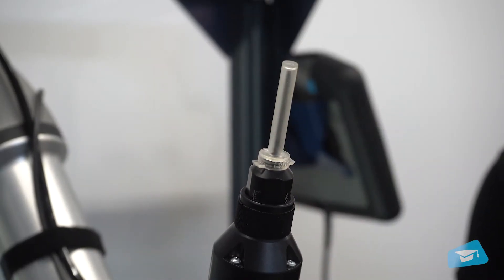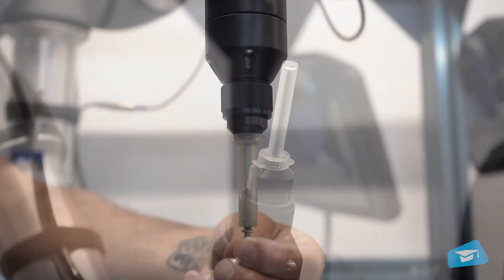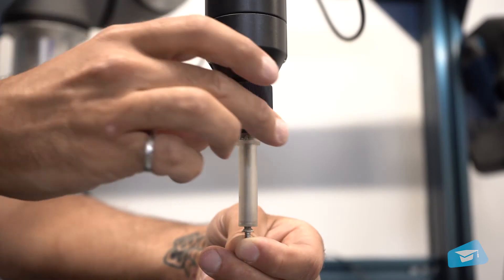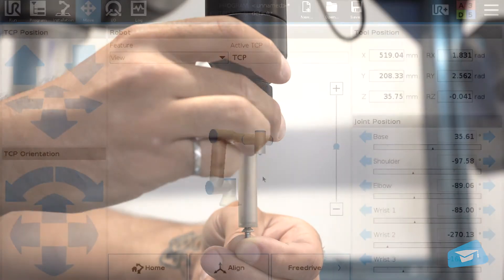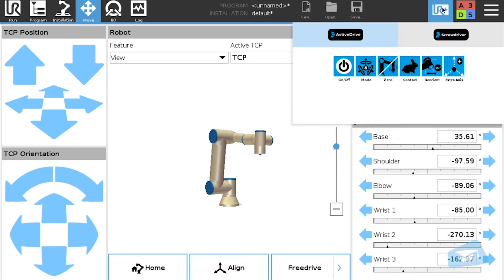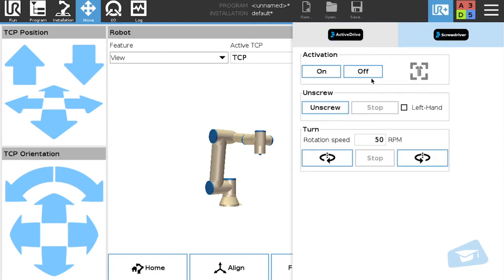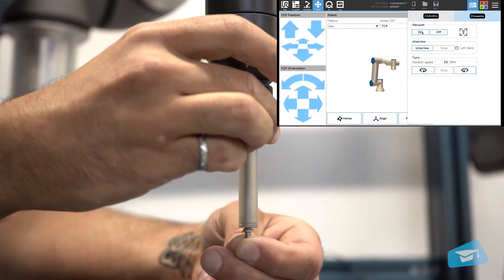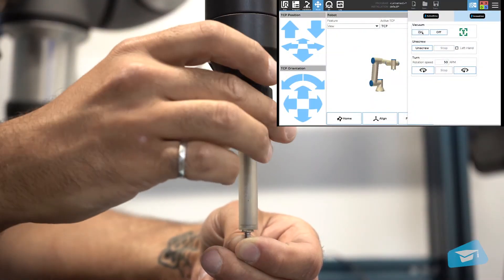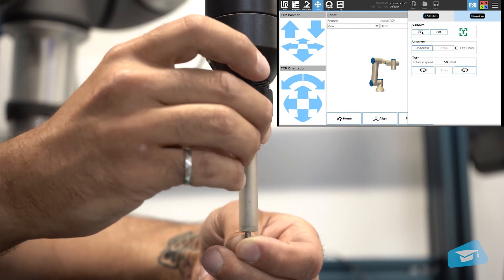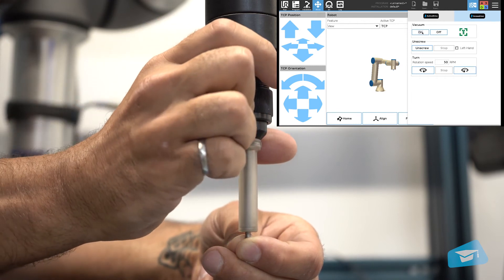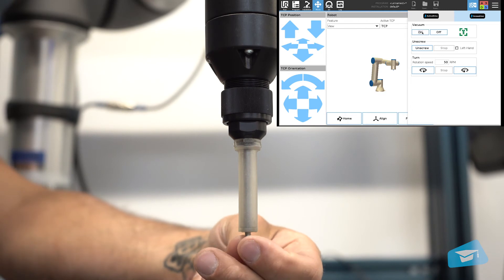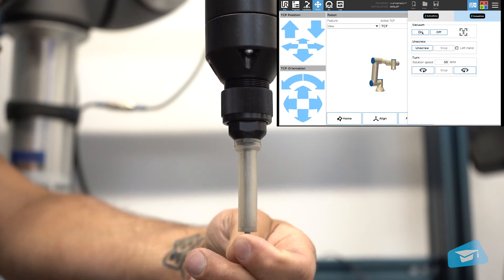The position of the vacuum sleeve in relation to the bit should be adjusted. To ensure a successful screw pickup using vacuum action, start the vacuum action using the screwdriver toolbar on the robot's teach pendant. Make sure that the screw driving bit is engaged in the screw's drive and that the screw's head comes into contact with the tip of the vacuum sleeve. You should see the screw detected indicator appear in the toolbar.